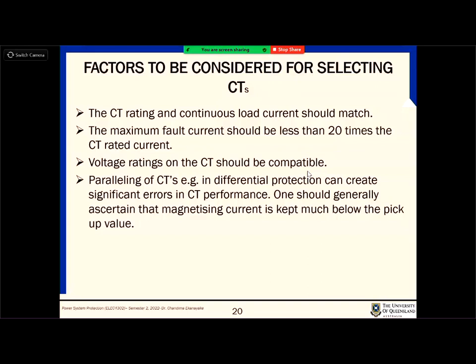And then when we are selecting a CT, we need to consider many factors, like voltage levels. What is the maximum fault current in the circuit? That's what we did in the calculations anyway. We looked at the fault currents, and then the CT ratings; basically the maximum fault current should be less than 20 times the CT rated current. And as I said, voltage ratio, and also that we need to look at if we need to parallel the CTs.